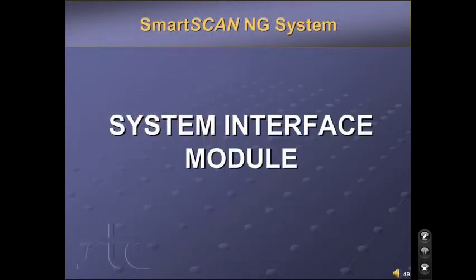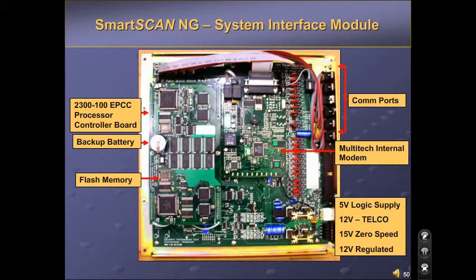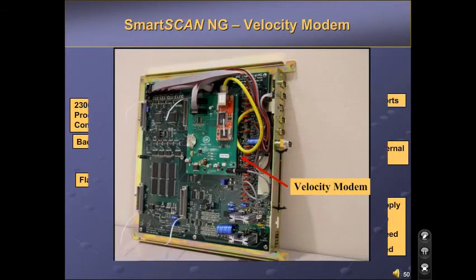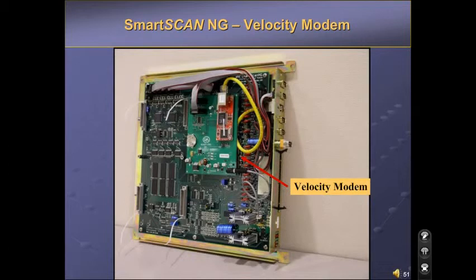Now, let's take a closer look at the System Interface Module. The 2300-502 System Interface Module is comprised of three circuit boards: the 2300-105 Interface Board, the 2300-100 EPCC Board, and the Velocity Modem Board. This picture shows the module with a Velocity modem installed. The COM3 DB9 cable has been replaced with an RJ45 plug. COM6 has a null modem adapter added to make it possible to connect to the Velocity modem with a laptop.